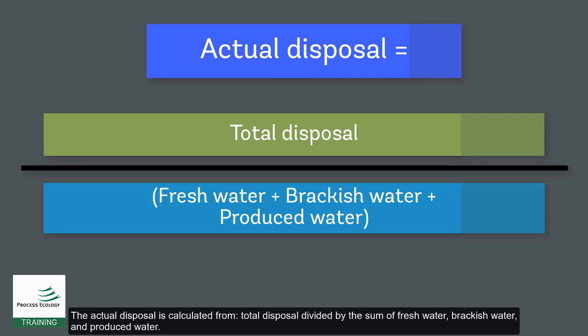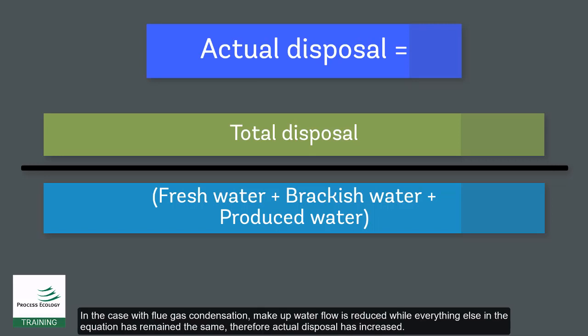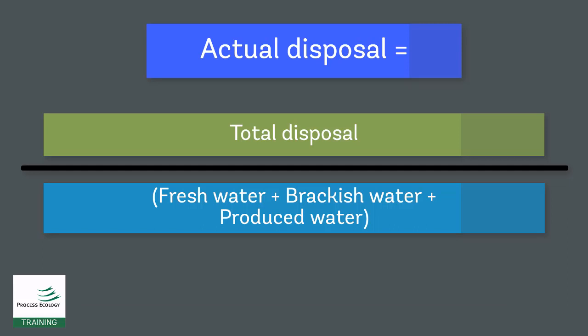The actual disposal is calculated from total disposal divided by the sum of fresh water, brackish water, and produced water. In the case with flue gas condensation, makeup water flow is reduced while everything else in the equation has remained the same. Therefore, actual disposal has increased.